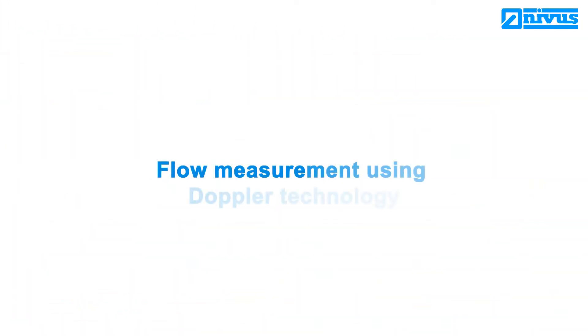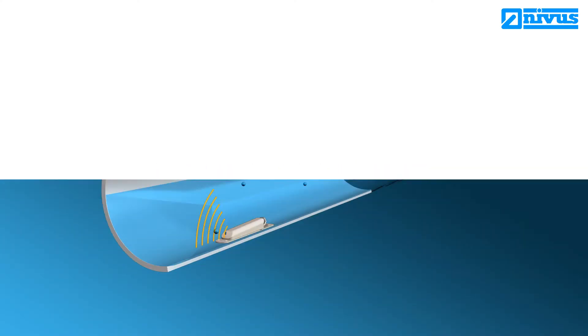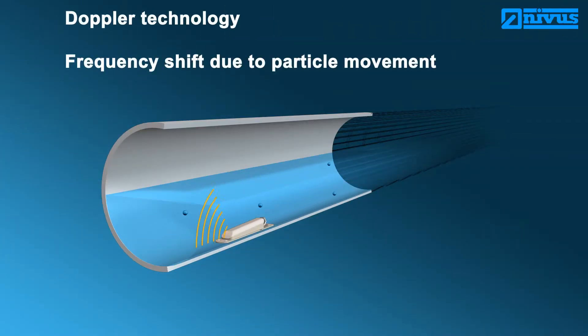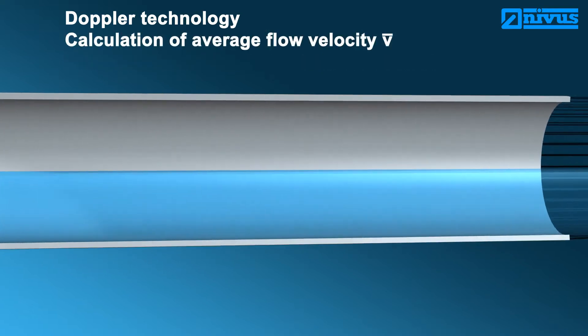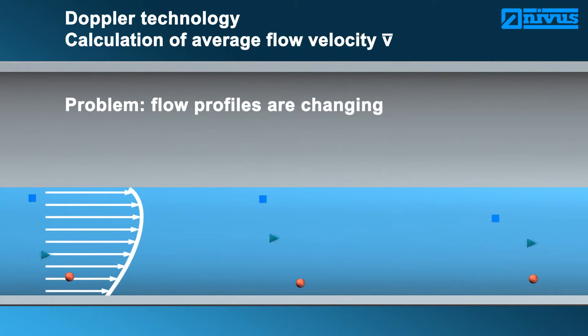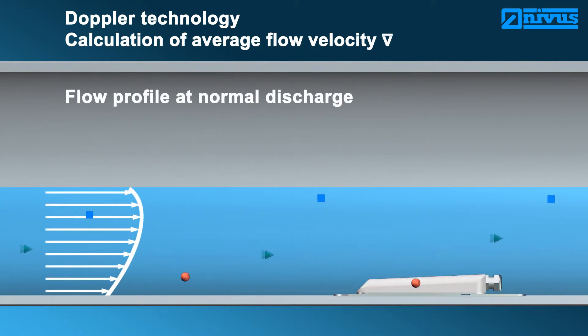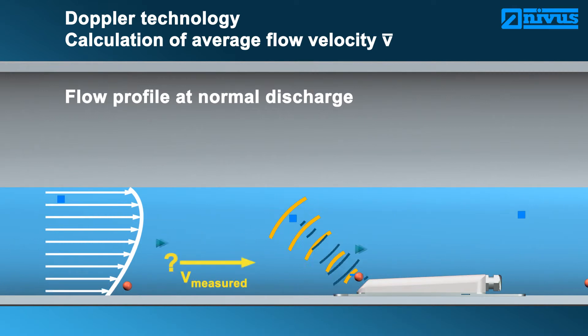Flow measurement using Doppler systems. The Doppler technology uses a sensor continuously transmitting ultrasonic signals at a constant frequency. The particles contained in the medium reflect the signal. The particle movement shifts the frequency of the reflected signal. The frequency shift is detected by the sensor — the greater the particle velocity, the greater the frequency shift. Doppler measurement is a spot velocity measurement; the sensor is not able to determine at which level the velocity has been detected, and due to this reason the flow profile cannot be represented.